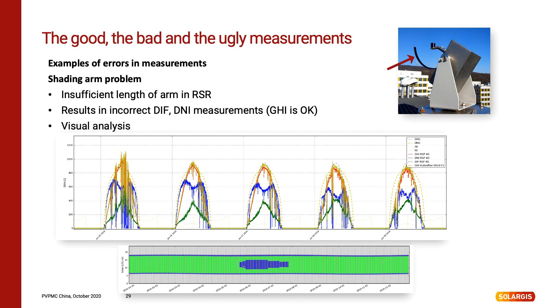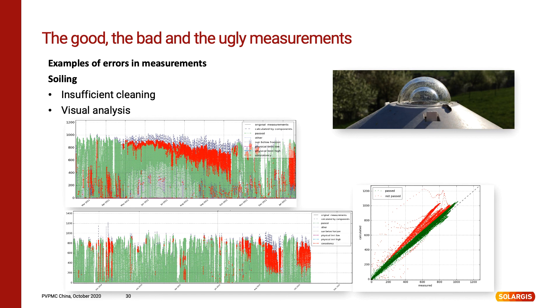In RSR instruments, direct irradiance is calculated from measured global and diffuse irradiance. So this fault resulted in wrong DNI measurements. It has to be noted that the consistency check is not able to detect this type of error. Insufficient cleaning is often a problem of measurement campaigns. Here the red color shows a slow degradation of measurements due to dirt on the sensor. At a certain point the sensor was probably cleaned, so after that point we get back to good measurements. This defect is also detectable on scatter plots when measured data are compared to calculated values.